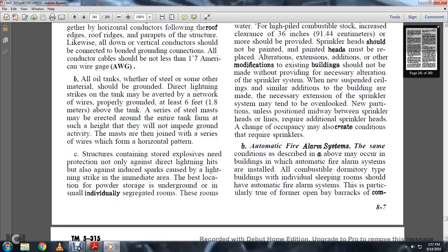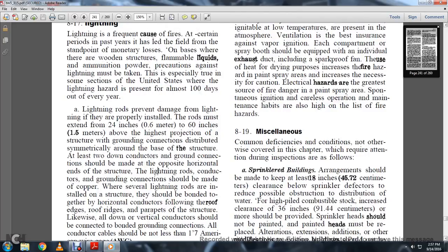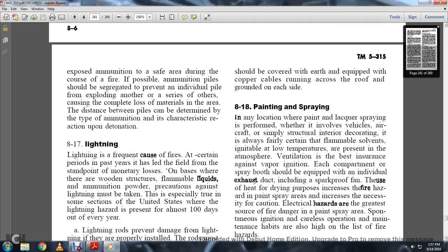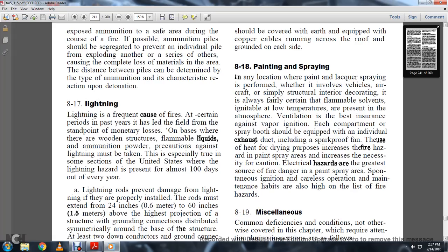Structures containing stored explosives need protection not only against direct lightning hits, but also against induced sparks caused by lightning strikes in the immediate area. The best location for powder storage is underground, in small individual segregated rooms. The room should be covered with earth and equipped with copper cables running across the roof and grounded on each side.